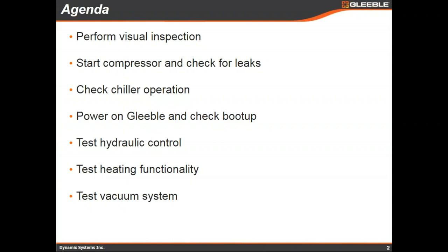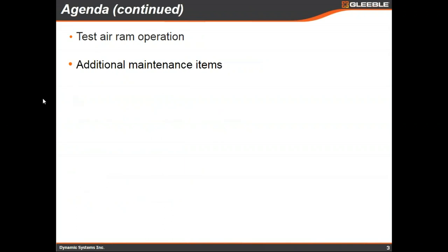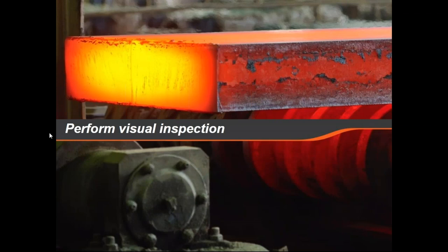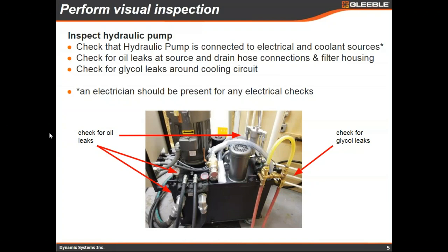We'll want to check the compressor, power the chiller, and power the unit itself back up. Once it's up, we'll verify the hydraulic system works, the heating system works, and the vacuum if so equipped — which I expect most systems have. Air ram is an additional worthwhile check to confirm the pneumatic system is working, followed by additional maintenance items prudent to cover at this time.